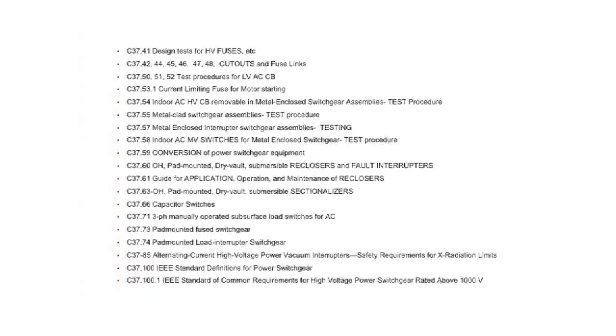I don't know if I have, there are even some very specific standards. Let's see if I had one here. Oh, that's an interesting one. C37.85, for example. There's a standard that requires some safety checks on vacuum interrupters, because vacuum interrupters can potentially, under test, emit X radiation. So if I work with vacuum interrupters, particularly in the testing part, you better at least be aware of the X-ray limits for these kinds of devices. And so some of them are quite detailed. There's a lot of standards on testing and test procedures. Again, how you prove that the equipment is good or complies with whatever requirements.